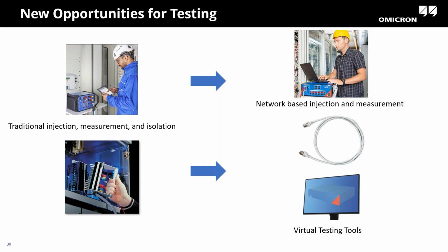But now we have new opportunities to do this in a different way. You're still going to need to test your power system. That's not going away. But when you're actually doing your testing, instead of needing to open physical test switches, which have the potential to create safety issues, now you would be logically isolating your devices from the potential, which is a digital potential now.